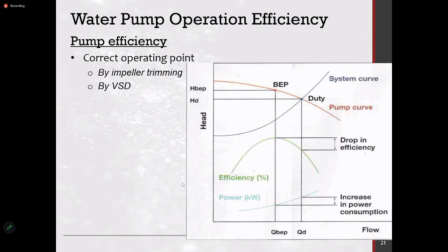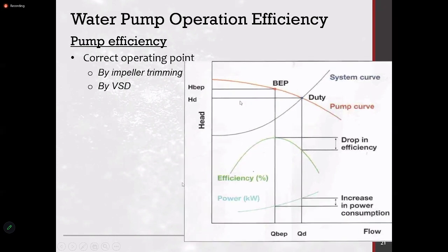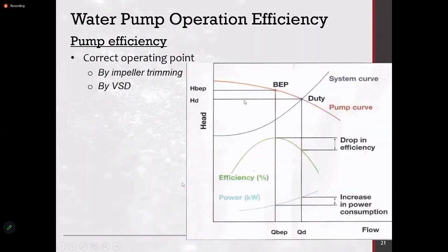Improving pump efficiency. So this is a typical pump curve, which you have to drill down from the pump supplier. They are also very reluctant to provide it, but nowadays you can, because efficiency is a concern. In those days you actually gave the size of the pipe and got the pump.